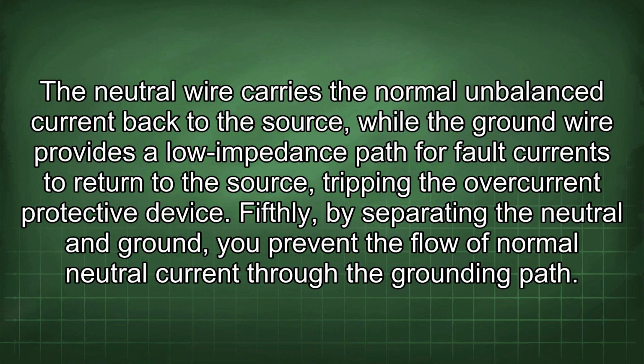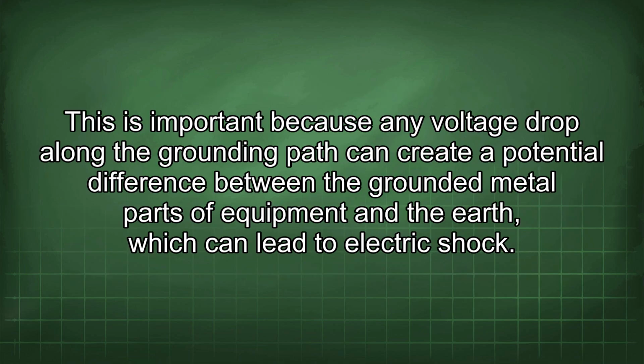The neutral wire carries the normal unbalanced current back to the source, while the ground wire provides a low impedance path for fault currents to return to the source, tripping the overcurrent protective device. Fifthly, by separating the neutral and ground, you prevent the flow of normal neutral current through the grounding path. This is important because any voltage drop along the grounding path can create a potential difference between the grounded metal parts of equipment and the earth, which can lead to electric shock.